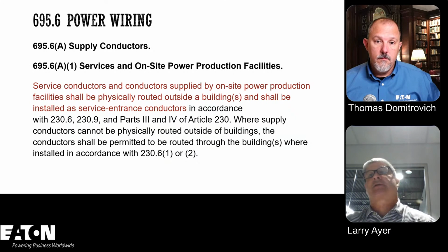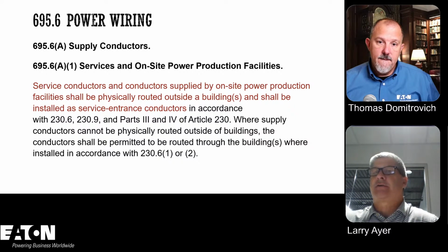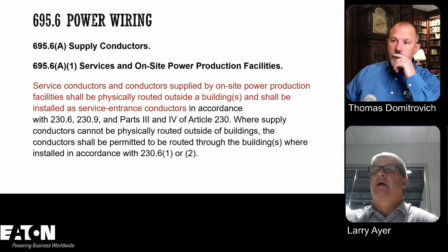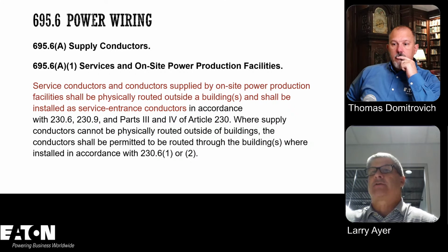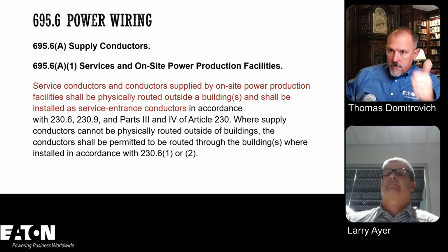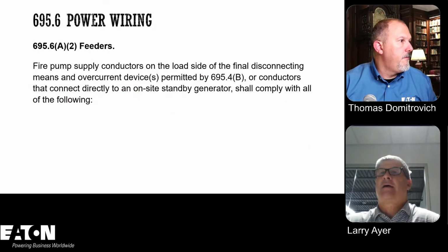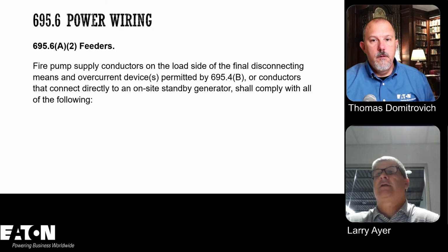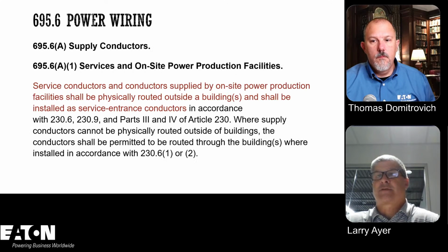Correct. So again, the service conductors are not really protected, like the NEC protects conductors a lot more closely to their ampacity than maybe a utility company does. Maybe the utility company wants to have a little bit of fat in there for nuisance tripping and for economic reasons. And so we need to make sure that when we look at service conductors, that we're tapping off a transformer going directly to the fire pump transfer switch, we do something special with them. And if we do that, we need to make sure that we route them outside the building. Yep. Now that is both on-site power production facilities and service conductors.